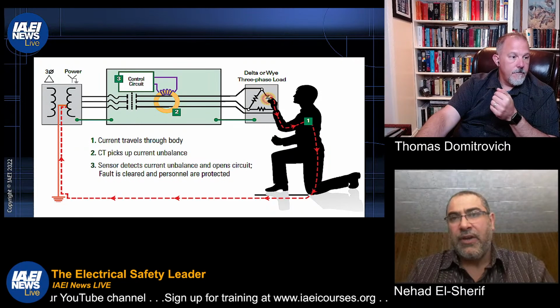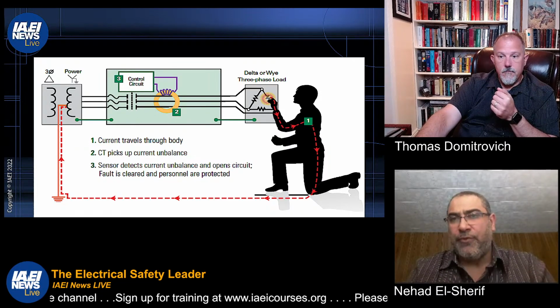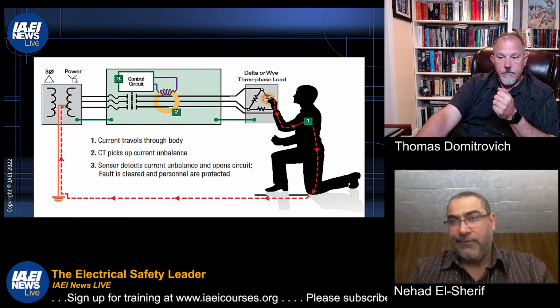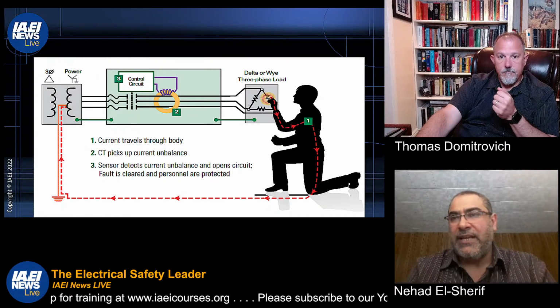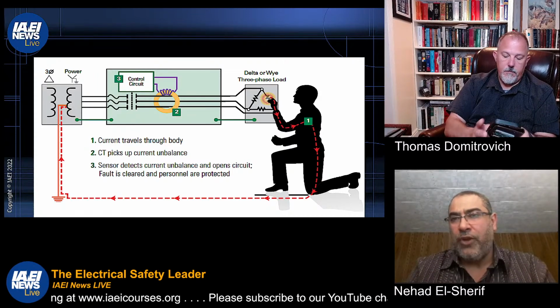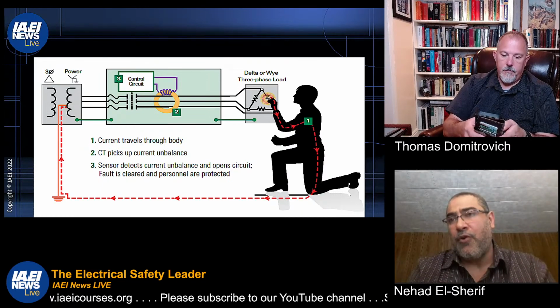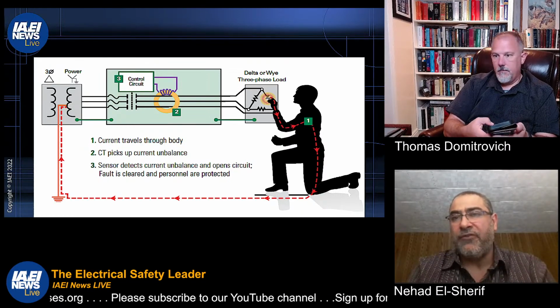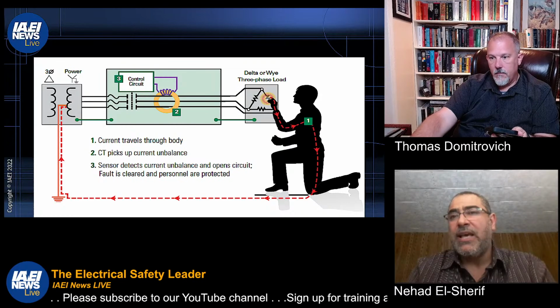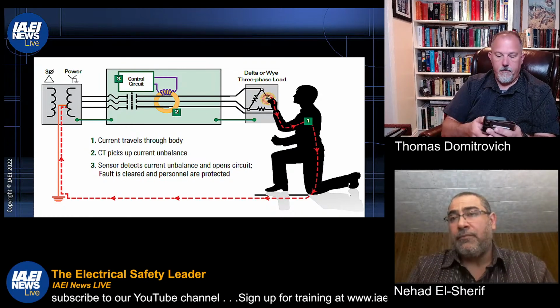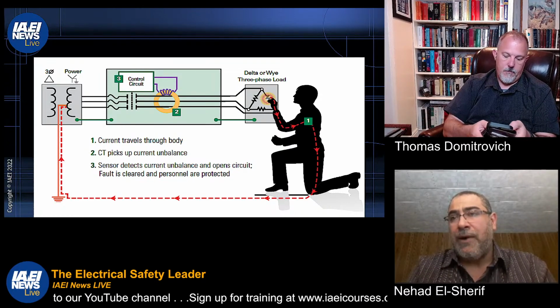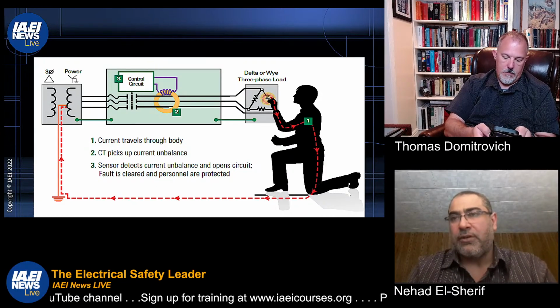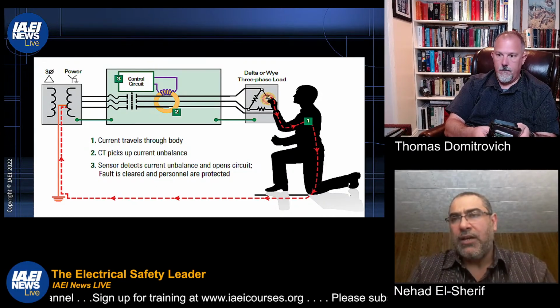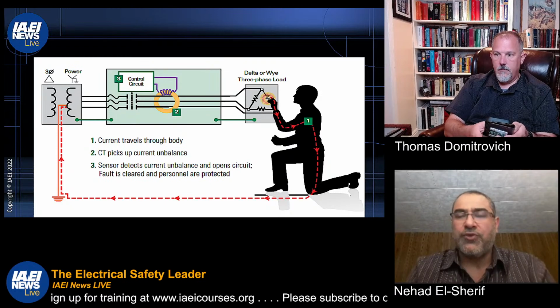You have all the currents going through a current transformer, like a zero sequence current transformer, or the donut, we call it. And if there's any differential, if the current going to the load is not exactly the same amount going back from the load, then the device would detect this difference and would trip in a time proportional to the amount of difference, or the leakage current that is happening, which we'll be showing in a couple of slides to answer Don Ganier's question as well.